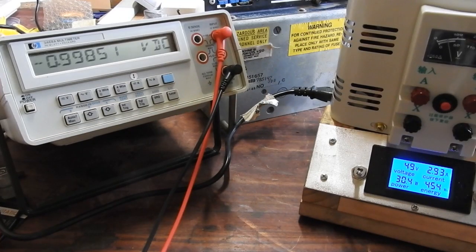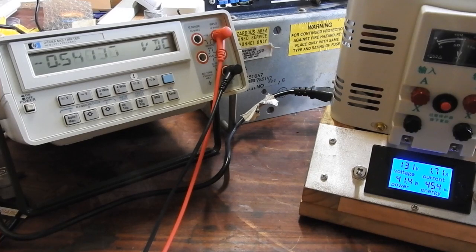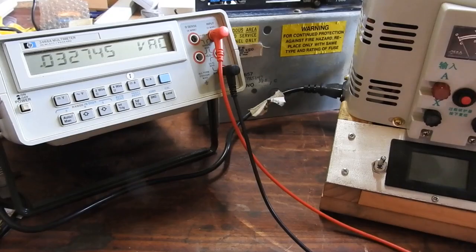And, apparently that's one of the features of ferroresonant transformers. They're noisy. There's only 50 volts going in and listen to the hum. And, it's drawing 1.7 amps with no load. Another feature of ferroresonant transformers.